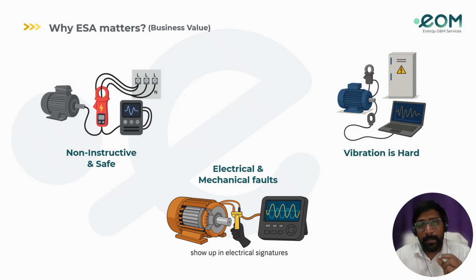And it works where vibration is hard, like inaccessible or harsh locations such as submerged pumps, or where you already have current transformers. For example, in a chilled water plant with submerged pumps, ESA is run remotely from the switchgear. So a rising bearing-related modulation on the current prompts a seal and bearing replacement to be done during the scheduled chiller shutdown. So there will be no lost cooling as well.